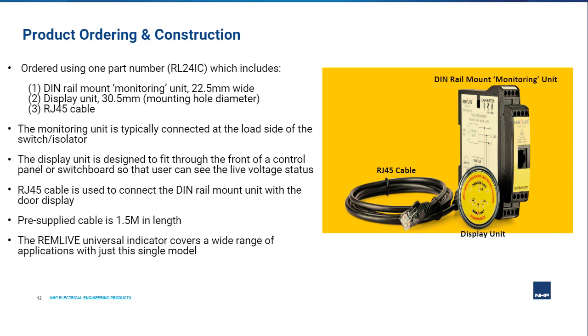This includes the DIN rail mount monitoring unit, also known as the base unit. Then there is the display unit and a RJ45 cable used to connect the monitoring unit together with the display. The monitoring unit is mounted to DIN rail inside a switchboard or control panel and has a standard 22.5mm width size. This unit is typically connected at the load side of the isolating device.